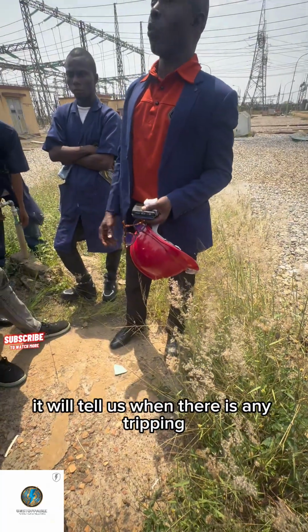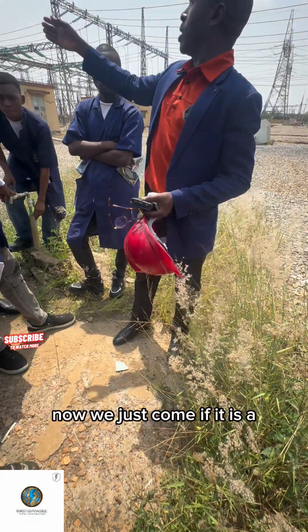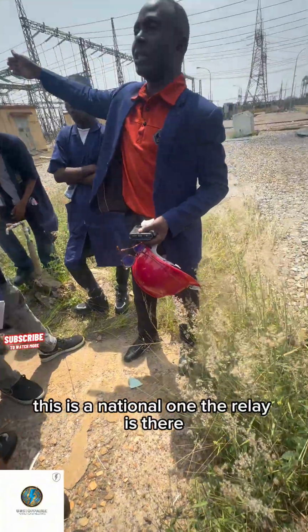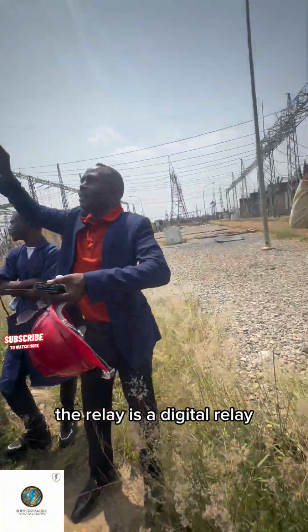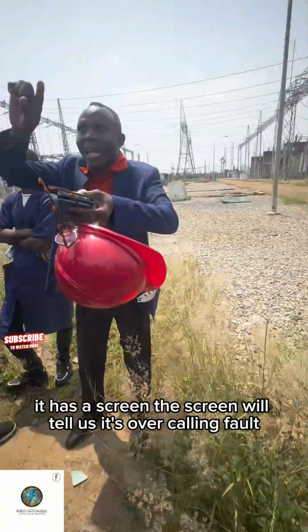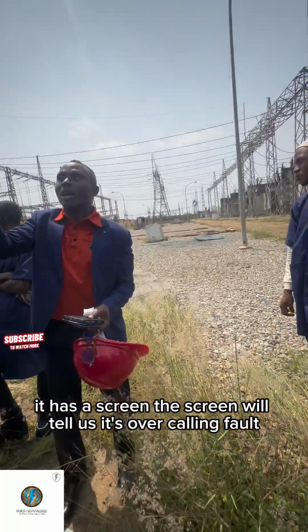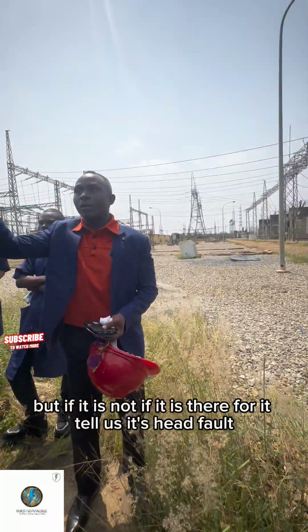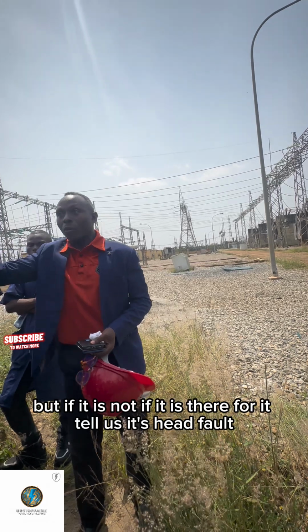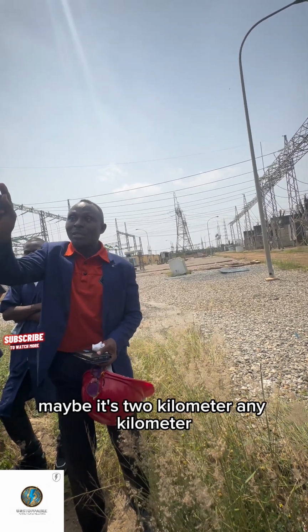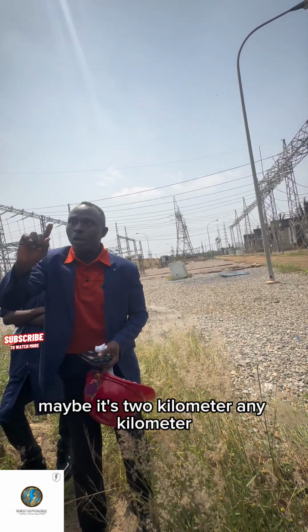Yes. At the control room now, it will tell us. When there is any tripping, we just come to this one. The relay is there. The relay is a digital relay. It has a screen. The screen will tell us if it is an overcurrent fault, or if it is a earth fault, it tells us it's an earth fault. And it tells us the distance. Maybe it is 2 kilometers. Any kilometer, it will tell us.